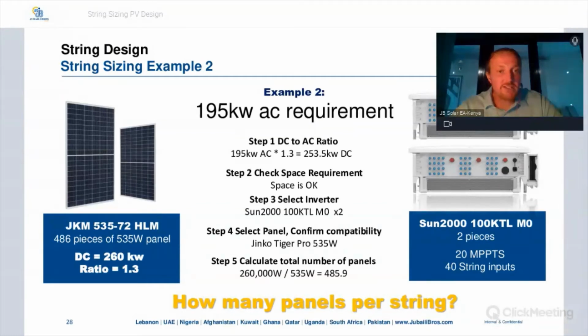Step 4 is you check the panel and confirm the compatibility. You check the data sheets, the max current per MPPT and the max power current of the panel, and you check the compatibility. We've done that and it works. It looks good. Step 5 is you calculate the number of panels you need. If you take 260 kilowatts and divide by the size of the panel, you get approximately 485.9 panels. So that's what we're looking at, around 485 panels.